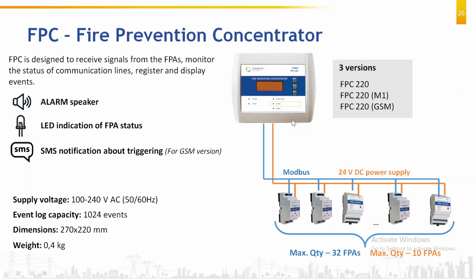And what is the thermal withstand capacity of FPA? Suppose I install the FPA in the cable chamber itself, and there is a short circuit or flashover, a huge amount of energy will be released, and heat will be there. So how much is the thermal withstand capacity of FPA? Sir, it's not designed to withstand fire or flash, but we'll have to see the data sheet. Okay, means if there is a flashover, we have to replace that FPA also. Yes. If there is a flashover, nothing can protect anything. Everything will go.